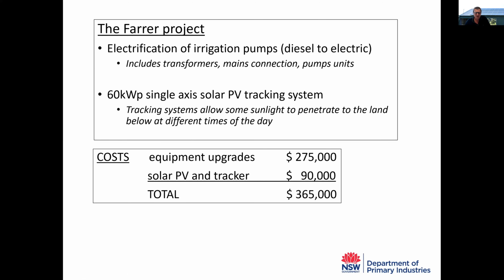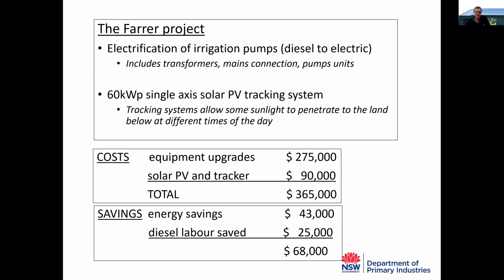The costs for this project: system upgrades were $275,000, and the solar PV and tracker were about $90,000, for a total of $365,000. Energy savings were $43,000, and labour and diesel maintenance savings were about $25,000, giving $68,000 total savings, for a payback of about 5.5 years.